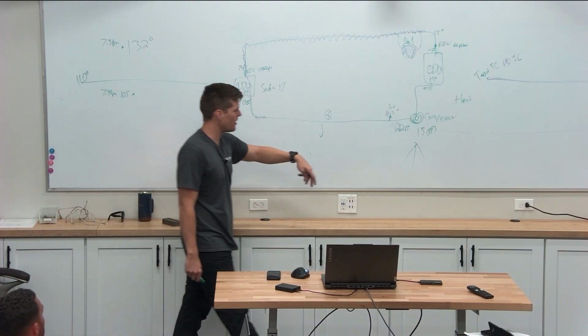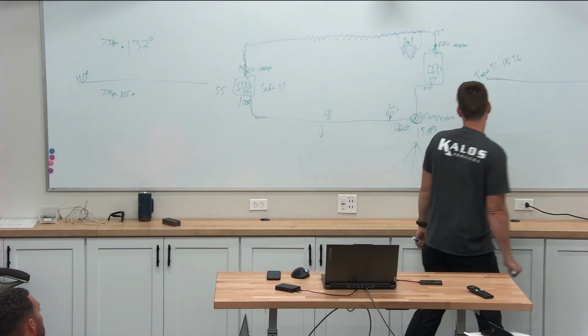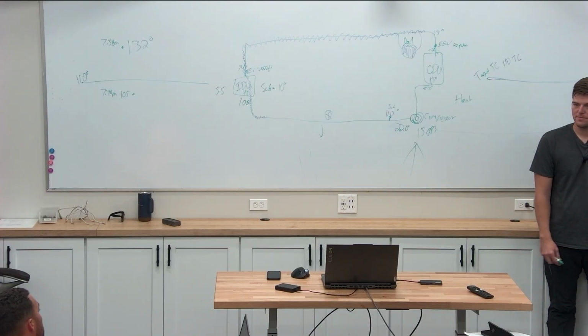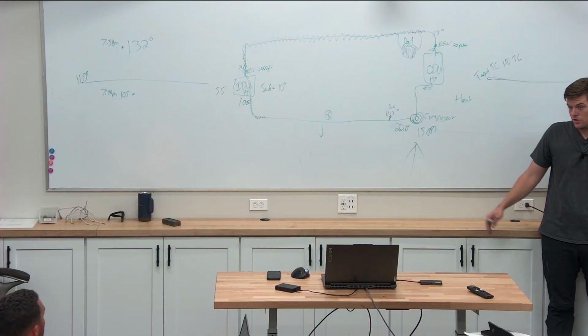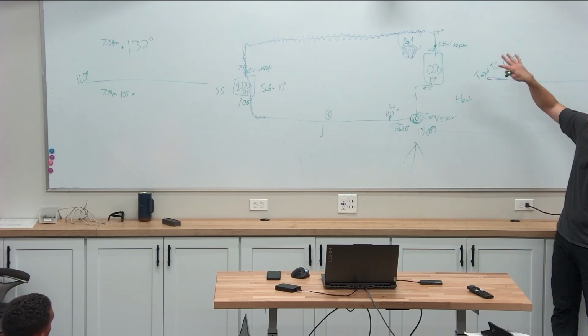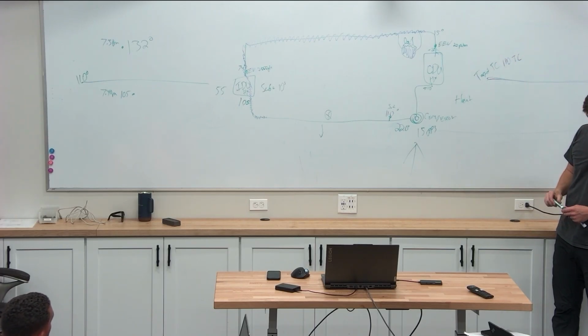Again, it's hitting its target. It's at 15 RPS, chugging along. If it goes any faster, it goes into high pressure step down, right? It's just got too much, too high pressure, right? Try not to give away the answer here. What's the last thing we need to know about this before we condemn it? Say they need a new system. It's not gonna fix it.